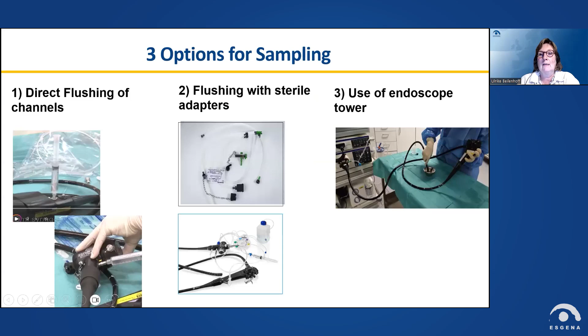I can do it with a direct flush of the channels, like it is shown here, and I can also use cleaning adapters or adapters to get access to the channels, or I can use the endoscope tower. So if I want to use direct flushing in some types of endoscopes, I can directly connect a syringe via a Luer lock or a Luer adapter. I can also use a long cone adapter to get access to the channel.